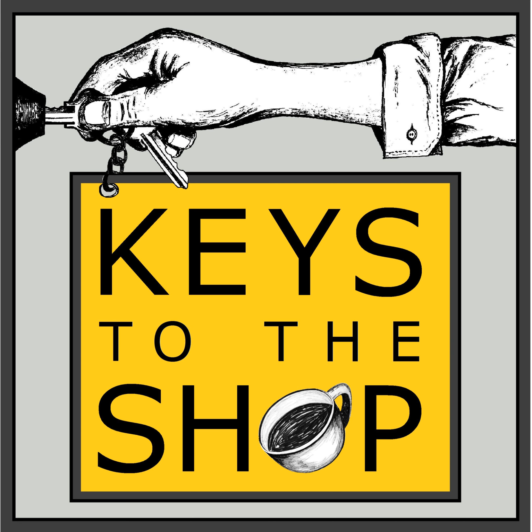Those are the things that actually overload an ice machine. Pulling the ice forward is beneficial for small shops that don't have a large enough ice maker for their demand. If you don't pull the ice forward, the ice will bind up or catch on the bin full switch or the ice bin damper and cause it to tell the machine to shut off. So pulling it forward just gives you a couple more pounds of ice in the machine during your off cycle.